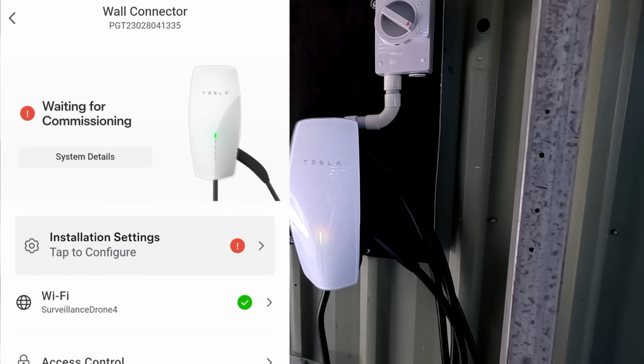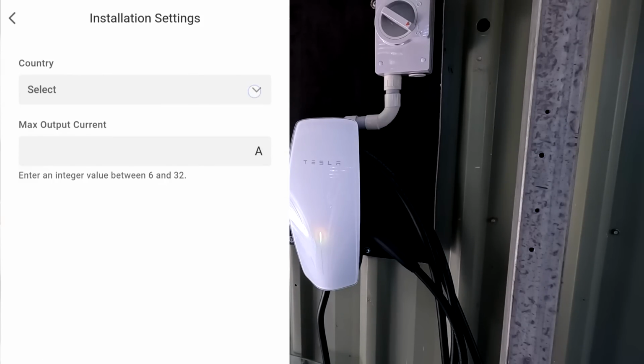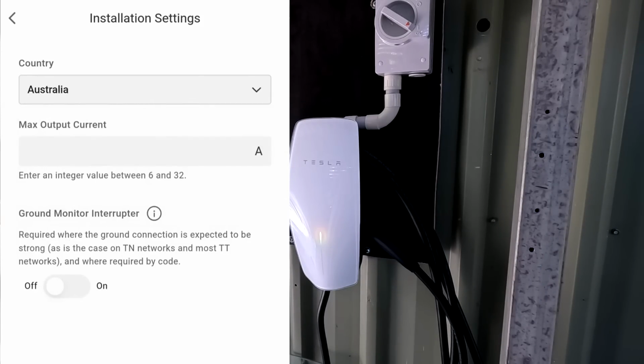Wi-Fi is already connected. Installation settings - select country, Australia. So here we can set our maximum output current. We have a 20 amp breaker installed, so we put in 20. And the ground monitor interrupter, yeah, we turn this one on as well here. This obviously only monitors the ground connection, and if it gets too high, it will disable the wall connector.